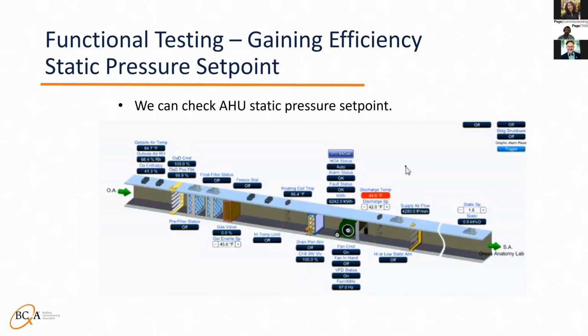Another thing to look at is the static pressure reset range, if applicable. The max set point on the static pressure range should be the same as the one in the TAB report. The static should never need to go above that value. The minimum set point can be 0. It doesn't really matter because if the static pressure reset is programmed correctly, it will reference all terminal unit damper positions, and if any go above 95%, it will stop resetting down. Also, the minimum speed setting on the VFD drive will prevent any issues with the fan motor.